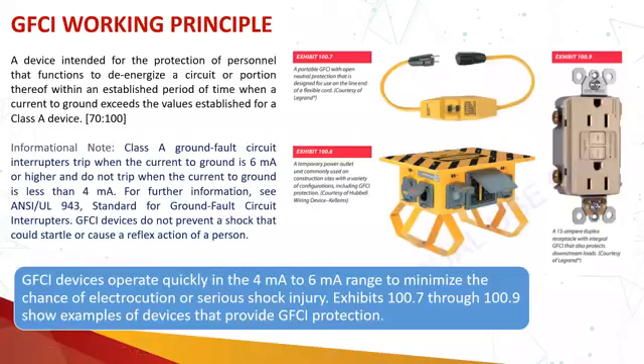So, working principles of GFCI. A device intended for the protection of personnel that functions to de-energize a circuit or portion thereof within an established period of time when a current to ground exceeds the value established for a Class A device. And here they have mentioned the normal setting of the GFCI as well. A GFCI device operates quickly, in the 4 milliampere to 6 milliampere range, to minimize the chances of electrocution or serious shock injury. Exhibit 100.7 through 100.9 shows examples of devices that provide GFCI protection. So there are different types of devices being shown, which are used at different locations.